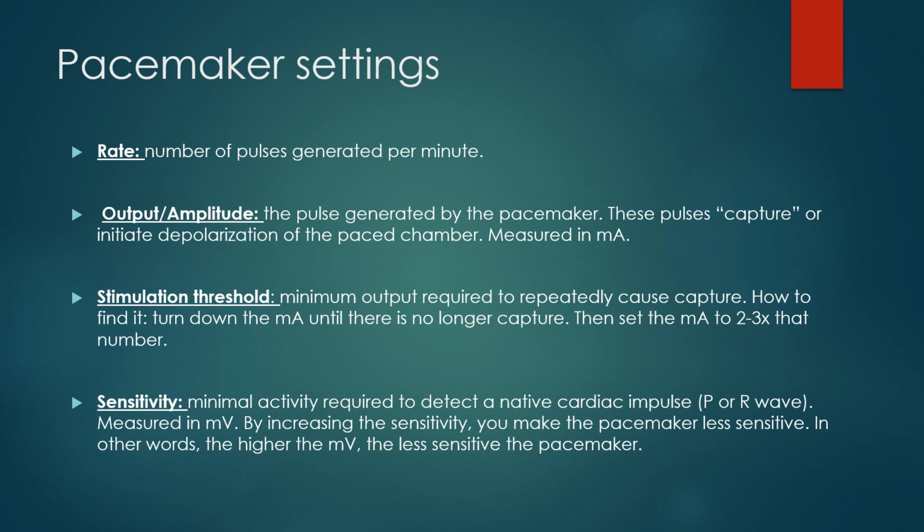The amplitude, or milliamps, this is how much shock, I'm sorry, how much do we need to deliver to get the pulse to capture, right? That's our milliamps. So it's how much are we going to shock them with? Okay, some need a little shock, some need a bigger shock.